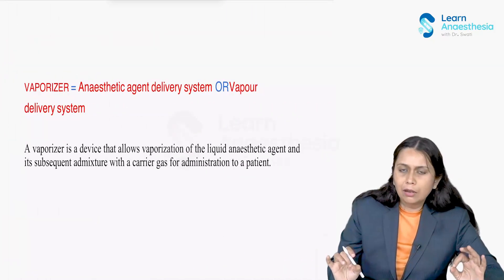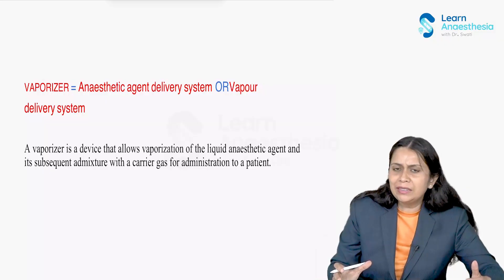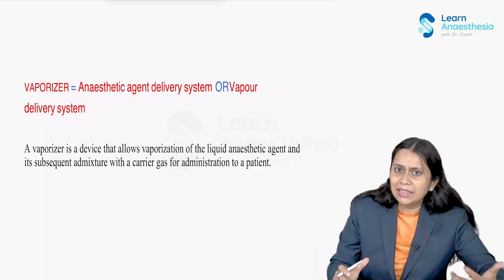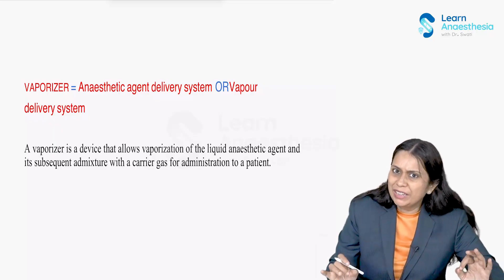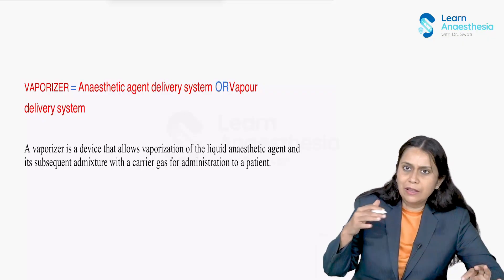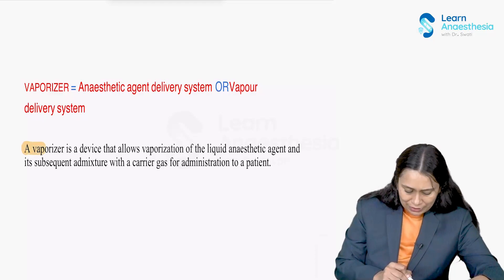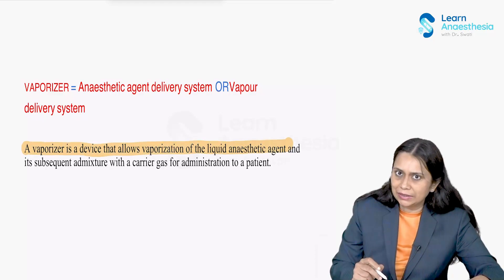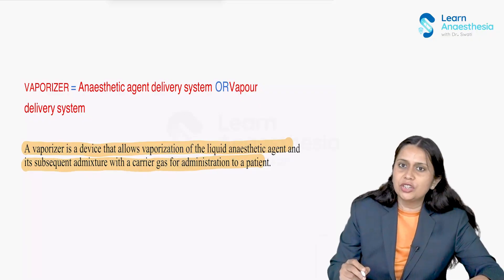Now let us discuss what a vaporizer is and how it is designed. A vaporizer is an anesthetic agent delivery system — specifically, an inhalational anesthetic agent delivery system or vapor delivery system. We define the vaporizer as a device which allows vaporization of the liquid anesthetic agent and its subsequent admixture with the carrier gas for administration to the patient.